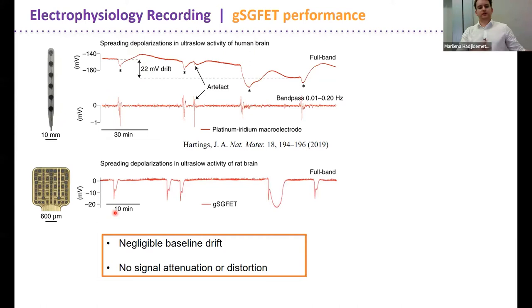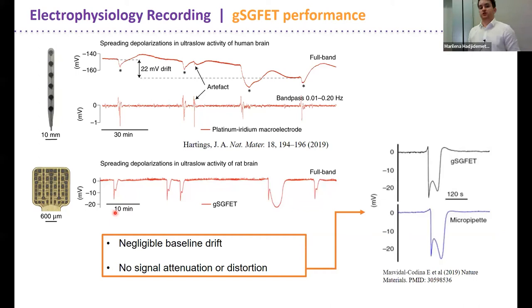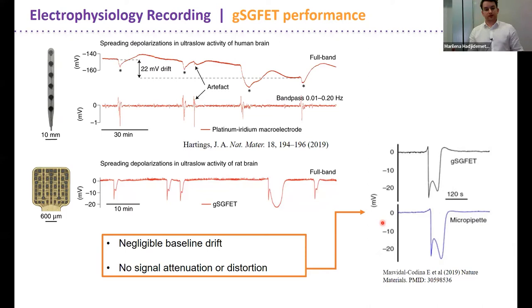How does this compare to previous devices? We see no signal drift when recording spreading depolarizations, and no signal attenuation or distortion — unlike the platinum iridium electrodes. We confirm this by recording the same depolarization simultaneously with the gold standard glass microelectrode placed next to the array. They show the exact same waveform and amplitude. We now have a technology combining the advantages of both platinum iridium and glass microelectrodes, with very high fidelity recording and spatial mapping capability.